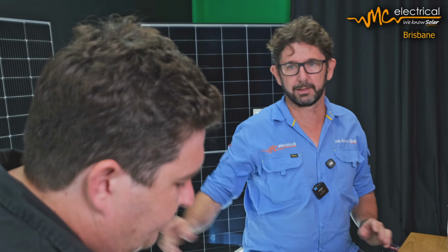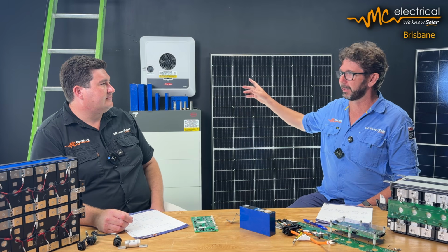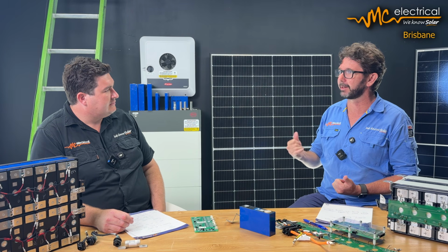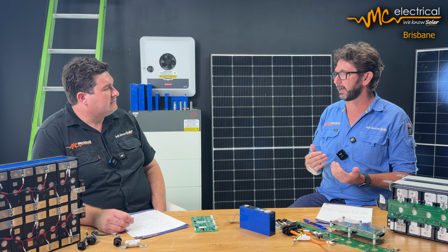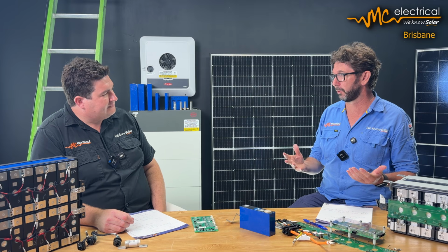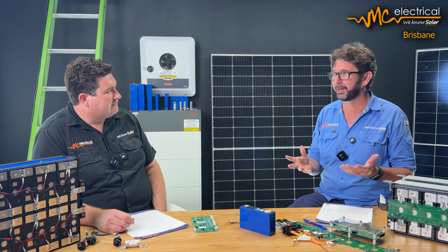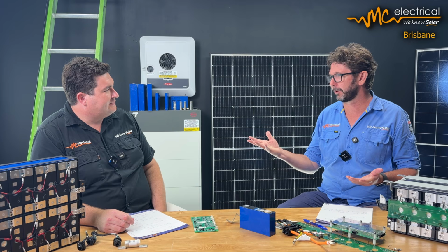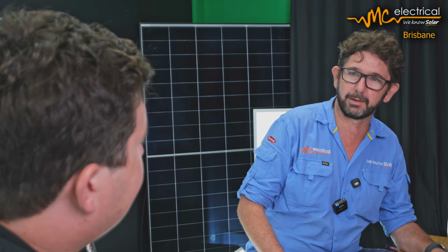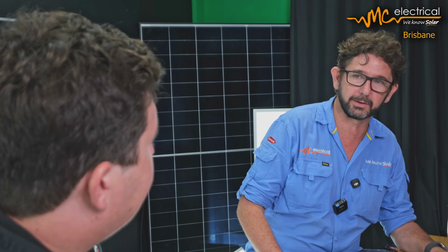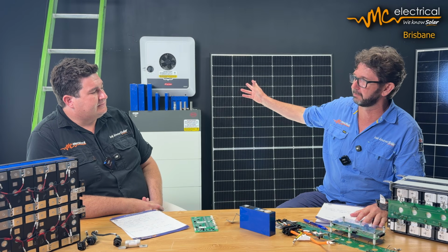Comparatively, if this thing is trying to discharge the battery really quickly, running 24/7, heating up in the middle of the day, it's going to heat up even more - maybe 20, maybe even 30 degrees hotter. And what do we know about the rule of thumb with power electronics, Joris? Every time it goes up by about 10 degrees, the life of that component is going to drop by about half on average. So we can't expect this inverter to run anywhere near as long as a quality inverter like Fronius. That's just what it is.